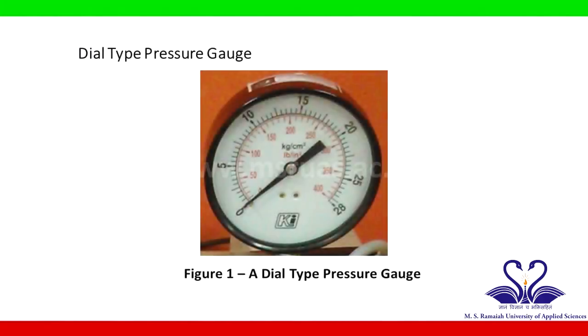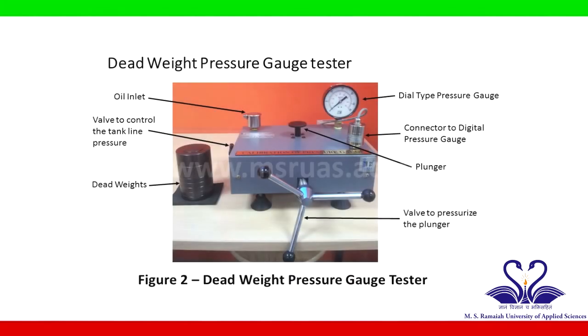Figure 1 shows a dial type pressure gauge. This pressure gauge is graduated in kg per centimeter square. Its range is 0 to 28 kg per centimeter square and it has a least count of 0.5 kg per centimeter square. Figure 2 shows the deadweight pressure gauge tester and its parts.